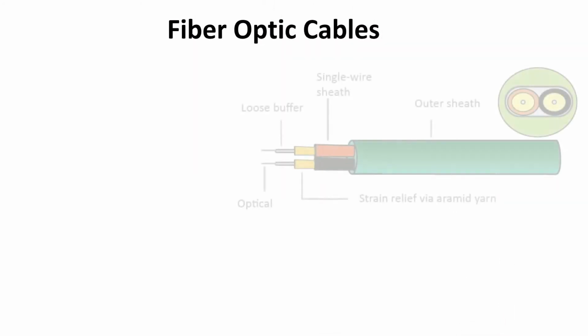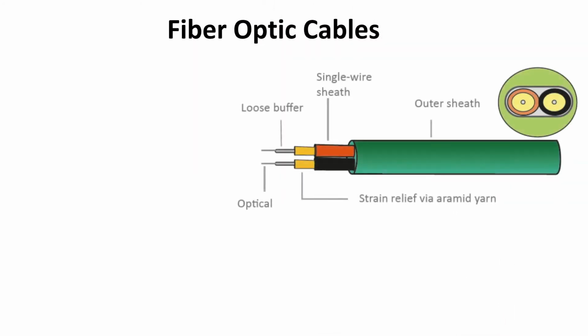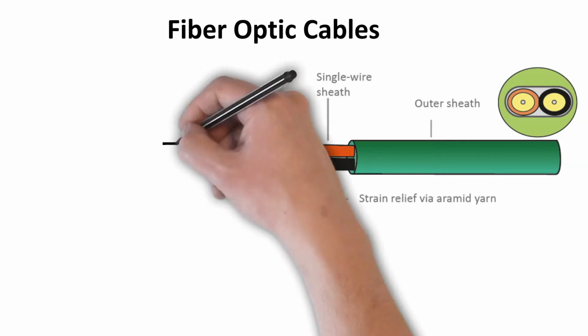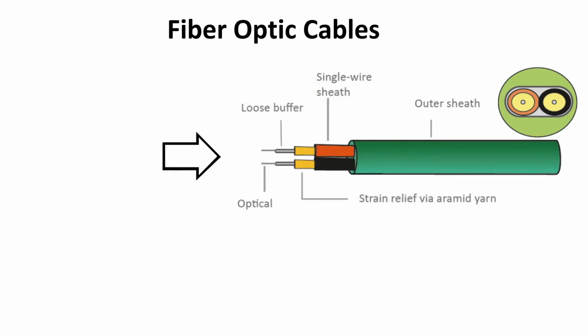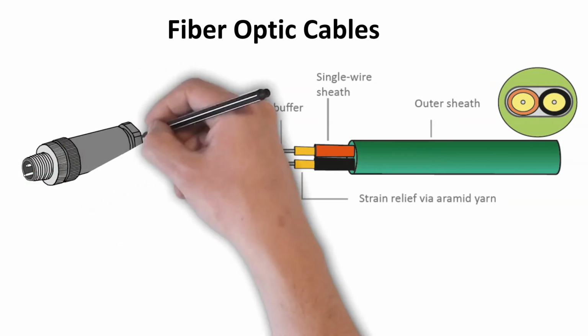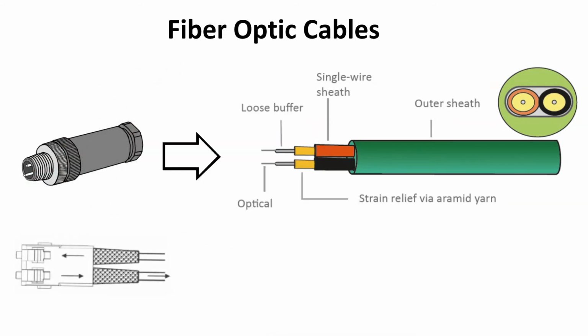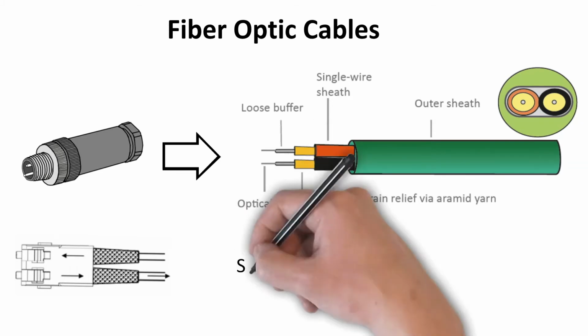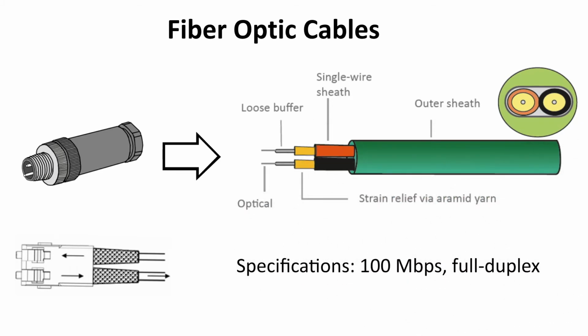Besides copper cables, Profinet can also employ fiber optic cables. The Profinet fiber optic cables scheme consists of two parallel wires. The wires are ready for the direct assembly of connectors. Printed directional arrows help facilitate the wire's assignment to the transmit and receive connections. Profinet fiber optic cables have speeds of up to 100 megabit per second and full duplex communication over two wires.